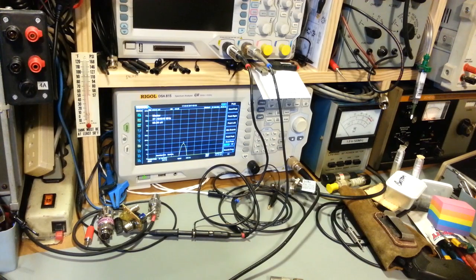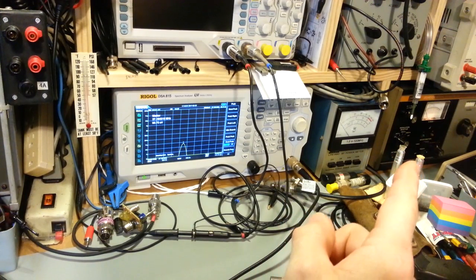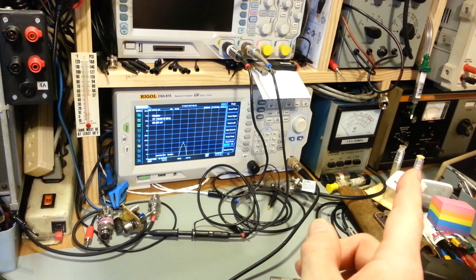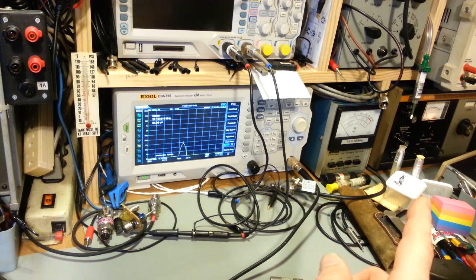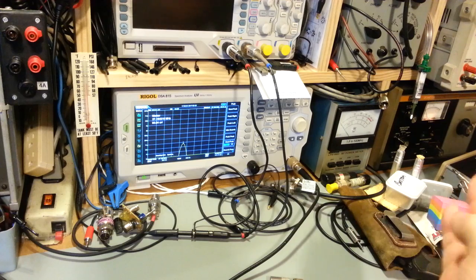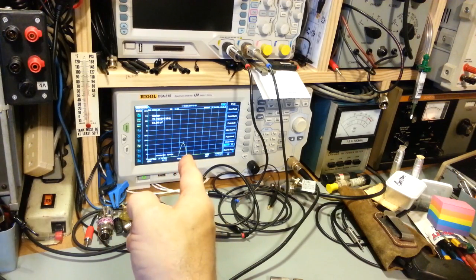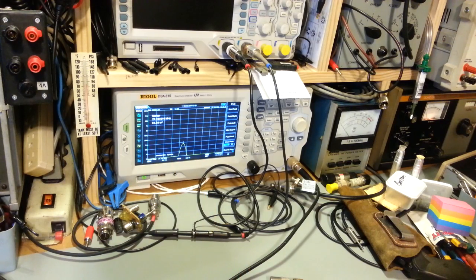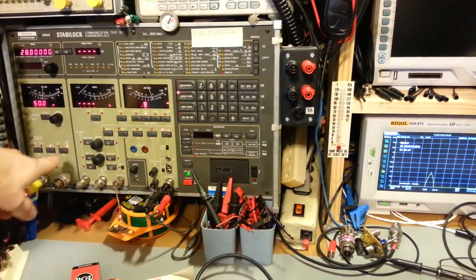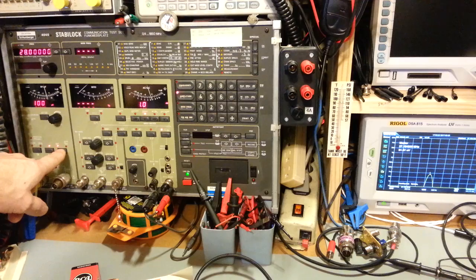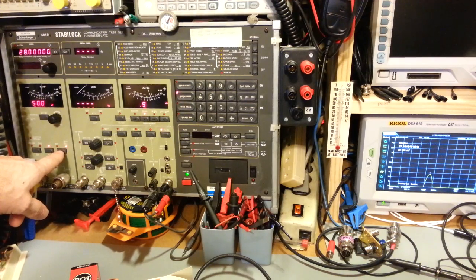So that's one of those things I have to be aware of. When I'm using that signal generator for my frequency or signal source, I have to make sure that when I'm calibrating a meter for S9, and the manual says 100 microvolts, that's exactly what I'd set it to on that signal generator. What I'll end up with is 50 microvolts into 50 ohms, or 100 microvolts EMF. If I am using this one, I just need to pay attention to this little red light here, whether I have it set to EMF or into 50 ohms.